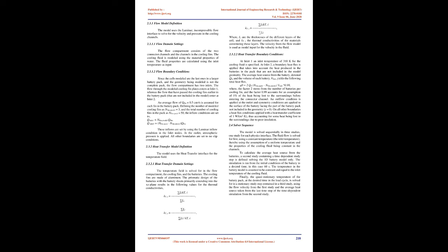2.3.2.1 Heat transfer domain settings. The temperature field is solved for in the flow compartment, the cooling fins, and the batteries. The cooling fins are made of aluminum. The prismatic design of the batteries, with the battery sheets primarily extending into the XZ plane, results in specific values for the thermal conductivities, where Li are the thicknesses of the different layers of the cell, and Kt,i are the thermal conductivities of the materials constituting these layers. The velocity from the flow model is used as the model input for the velocity in the fluid.